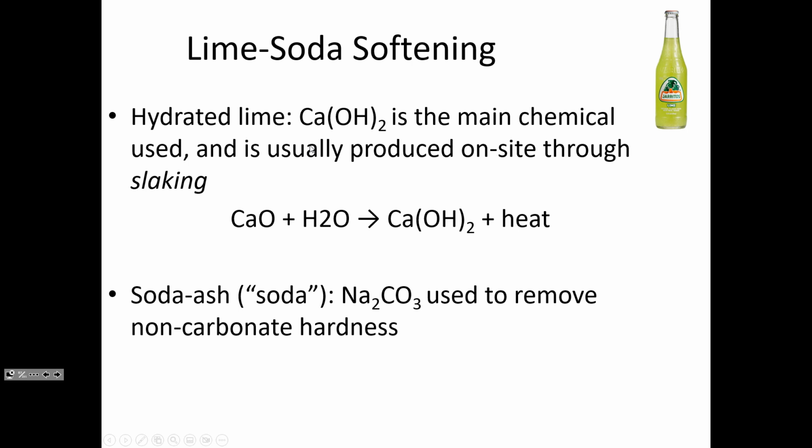But calcium hydroxide would have to come to a treatment plant as a liquid. And so it's just cheaper to deliver the precursor to hydrated lime instead. So through a process called slaking, if you bring powdered calcium oxide and mix it with water, then it will generate the hydrated lime. The thing is it's very exothermic.